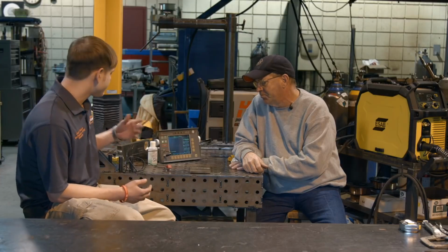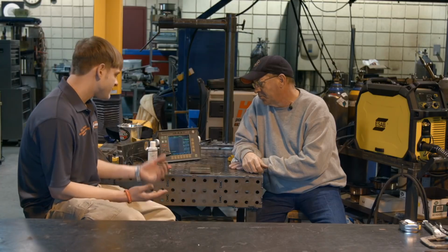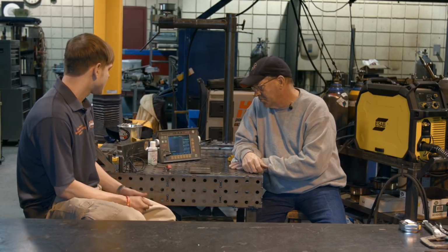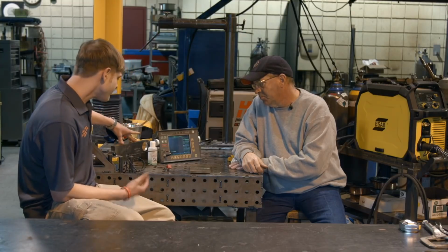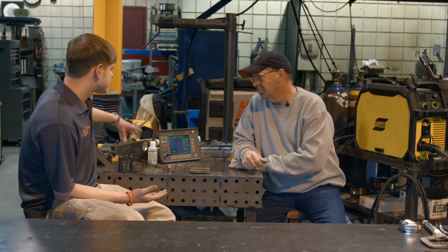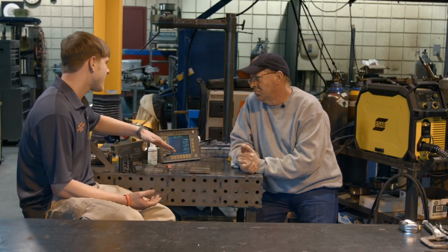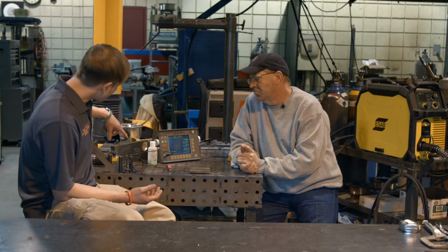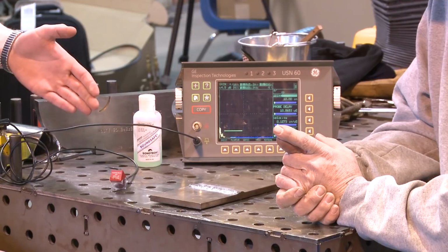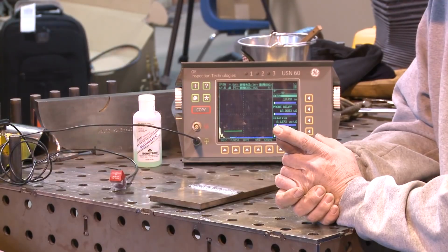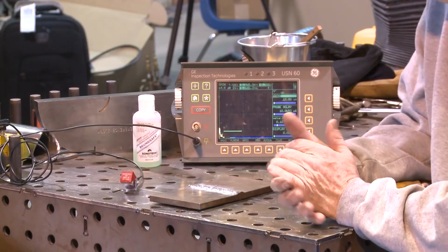Well, what I've already done is I calibrated my instrument here. This is a GE USN 60. It's a typical flaw detector. It's multi-purpose, does a lot of things for us. But I use this IIW block here, and the interesting thing about ultrasound is I have to know some things before I go and try and tell you things about what I don't know. For example, I calibrated distance using this radius because it's a 4-inch radius, so that I can tell you how far away from my transducer that flaw really is. This being a transducer? This being a transducer, yes, sir.